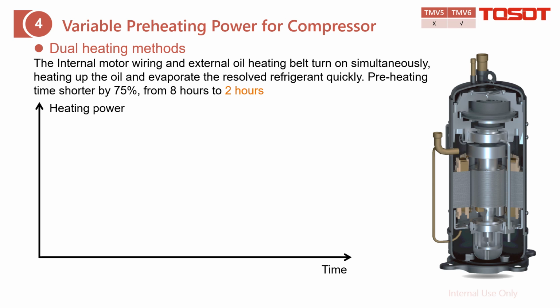Variable preheating power for compressor. For this topic, the purpose is to heat up the compressor before commissioning, which is to heat up the bottom oil located here. The purpose is that the refrigerant, which is liquid, and the oil are mutually soluble, which means they just mix together and we cannot separate them. In order to rotate the compressor, we need to avoid the liquid inside. But for this situation, it is impossible. So we need to heat the oil and make the liquid refrigerant become vapor or gas to flow out.